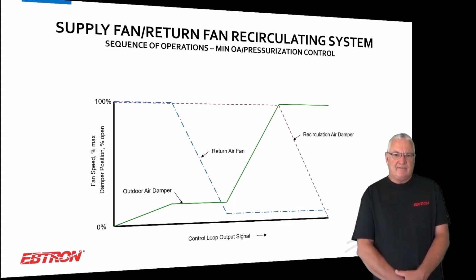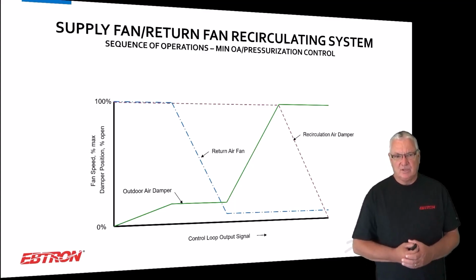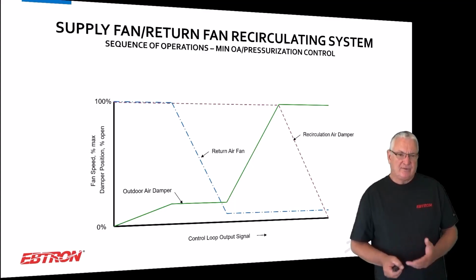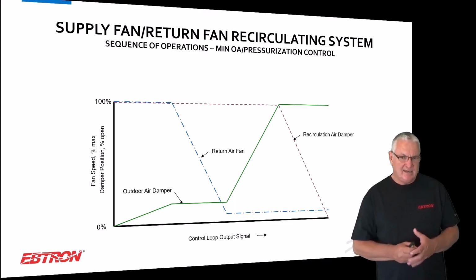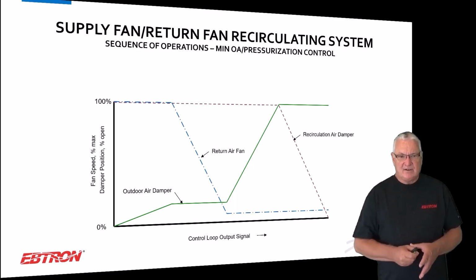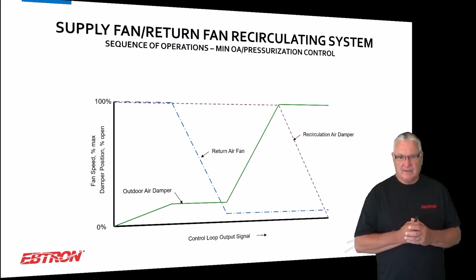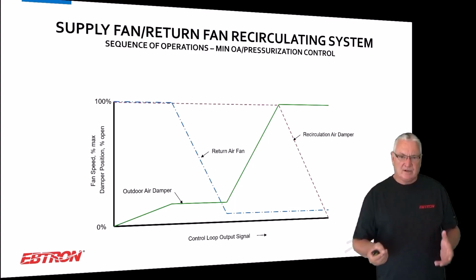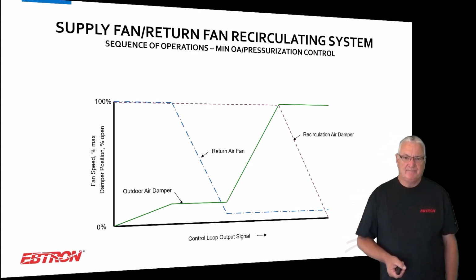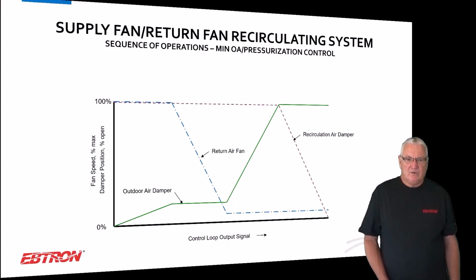When you don't have any relief at the air handler and we're trying to control this outside air, I want to take you from left to right. I have three things that I'm dealing with here. The green is the outdoor air damper, the blue is the return air fan, and the reddish color is the recirculation air damper, or the return air damper, whatever you want to call it. It's the same basic thing, but it's in the recirculation path, right? So the more outside air we need in this strategy, we're going to go from left to right. That's how this basically goes.